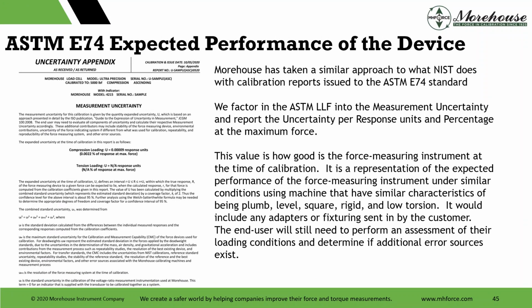So here's something else we do. NIST gives an annex, and we decided we like NIST. We really like them. So we take a similar approach to measurement uncertainty, which is done in the annex here. Here's our sample. If you've seen a NIST cert, it looks very, very similar. We copied a lot of it. They follow Technical Note 1297 from NIST. It's a very good method to say, with that lower limit factor, this is really the true expected performance of the device. We know you're going to derate it, but it includes the lower limit factor and the uncertainty of the reference standard. So it's the value of how good the force measurement is at the time of calibration.